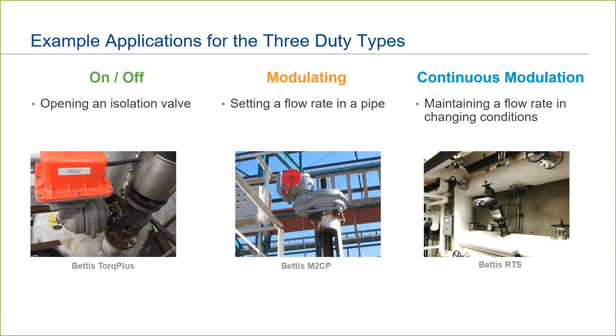For modulating service, we have an example of a Bettis M2CP on a pipe controlling flow rate of drilling fluid down into a well in the Middle East. Modulating service is not precise control, but at 1,200 starts per hour, we are able to maintain a basic flow rate in cases where precision is not required.